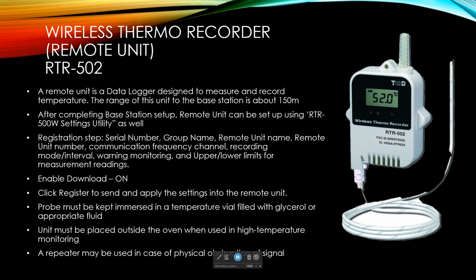After completing the base station setup, the remote unit can also be set up using the RTR500W settings utility in Windows. The registration step includes registering the serial number, group name, remote unit number, communication frequency channel, recording mode, interval, warning monitoring, and upper and lower limits for measurement readings, etc. You need to set the enable download to on, and once everything is set up, you can click register to send and apply the settings to the remote unit.